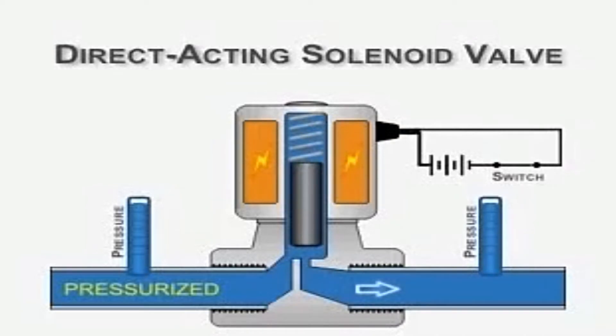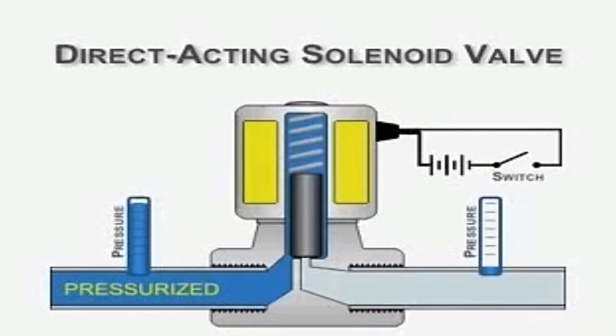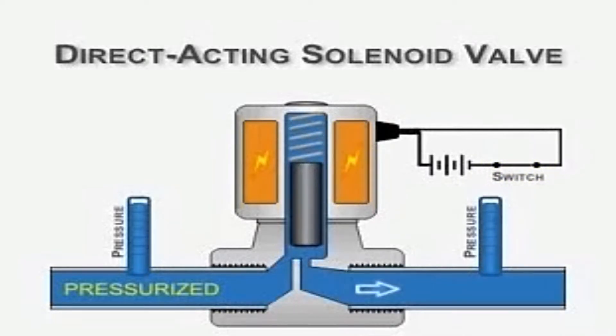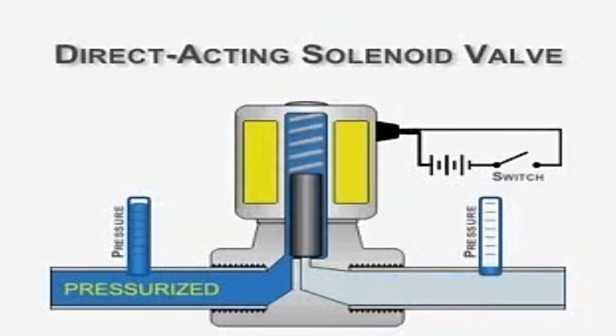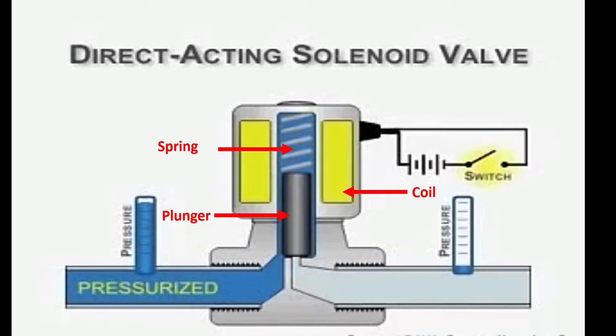When the power supply is de-energized, the coil immediately de-energizes and the plunger and spring move back to their original position, shutting off the process fluid. The upstream remains pressurized while the downstream gets de-pressurized. This is how a solenoid valve works: when the coil energizes it lifts the plunger, and when it de-energizes it releases the plunger back to its original position.